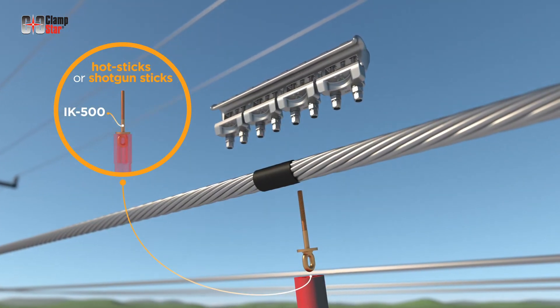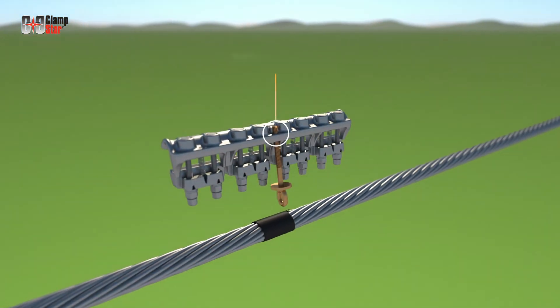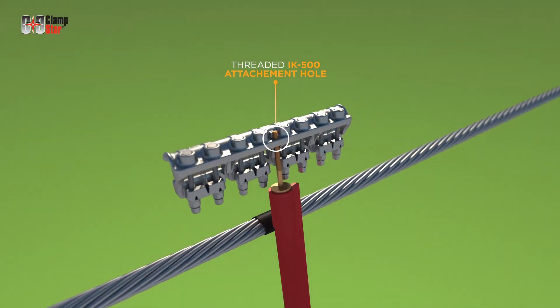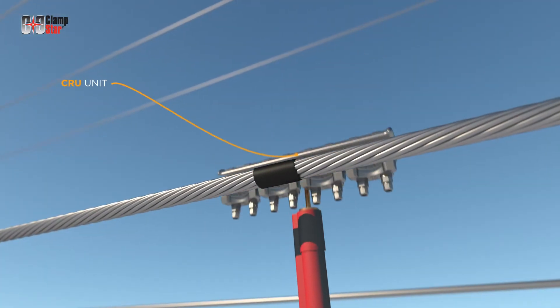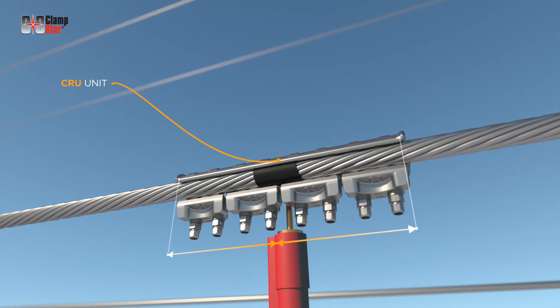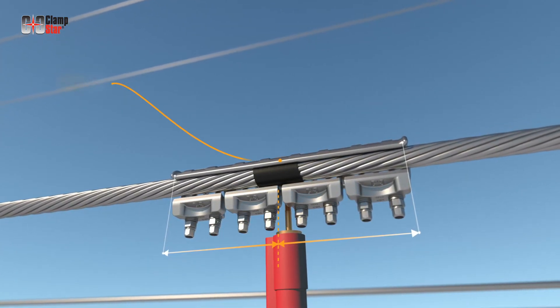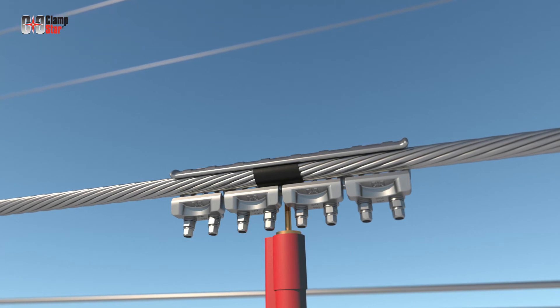Optional installation kits are needed for all stick installations and are attached by utilizing the threaded hole on the CRU unit. Place the CRU unit on the conductor with the damaged area centered between the left and right side of the unit. Once positioned on the conductor and to stabilize the ClampStar unit in place, simply leave the hot stick attached until installation is completed.